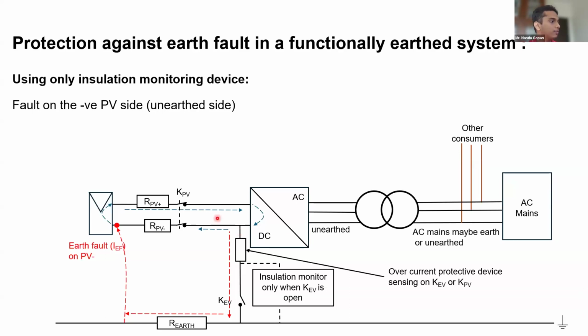He'll be able to know that there is a fault here, and he can rectify the fault. But suppose this R earth is compared to R PV is a little lower, then the current traveling in this path will be much more, and the overcurrent protective device will trip. So only if the R earth impedance is really large, such that the current flowing through is really low, and this overcurrent protective device doesn't trip, that is where this problem happens.